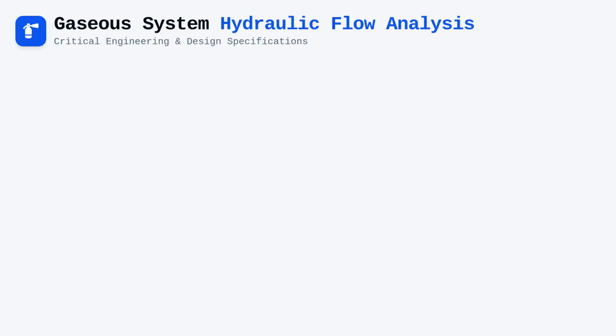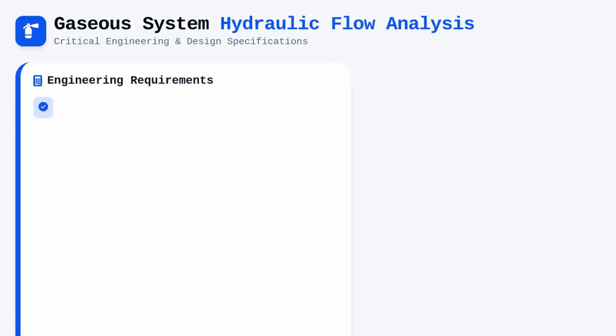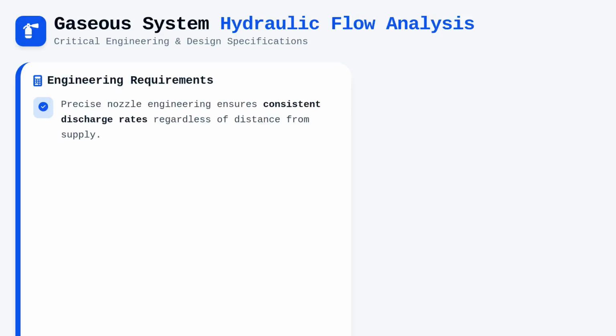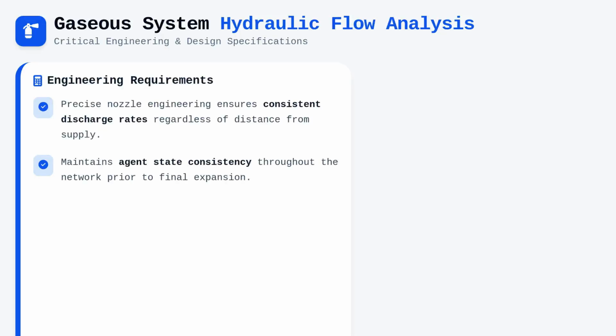Hydraulic flow calculations represent the most critical technical barrier in gaseous system design, as discharge nozzles are engineered for precise flow rates regardless of their distance from the agent supply. These calculations ensure that the agent remains in a liquid or gaseous state throughout the piping network until it reaches the discharge point, where nozzle orifice geometry manages the expansion.